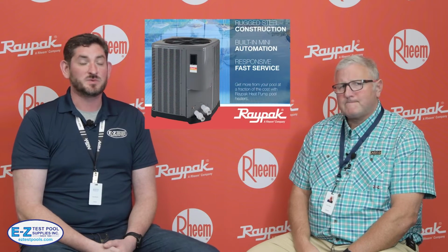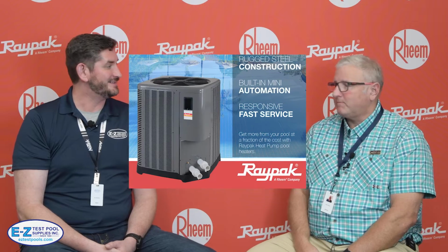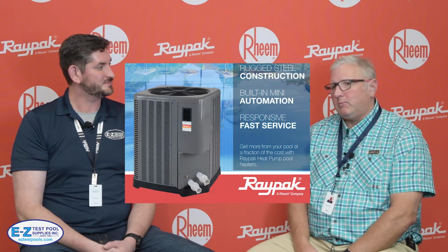Today we're going to be talking about the Raypak 8450 heat pump, one of our best-selling units. Gavin, why is that? I think historically, when pool heater sizing comes into play, people like the theory of being safer than sorry. The 8450 is actually 120,000 to 130,000 BTUs of energy, so you can heat most pools within a reasonable amount of time. And if you had a hot tub, you could do that as well. The theory behind heat pumps is to set it at your set point temperature and then leave it alone. Don't treat it like an on and off unit.